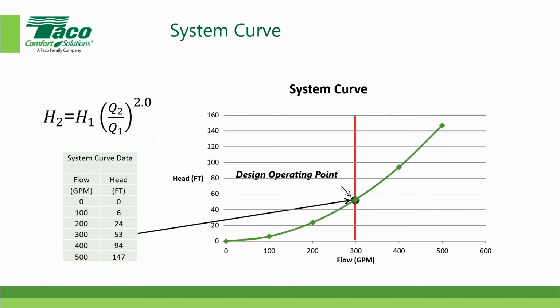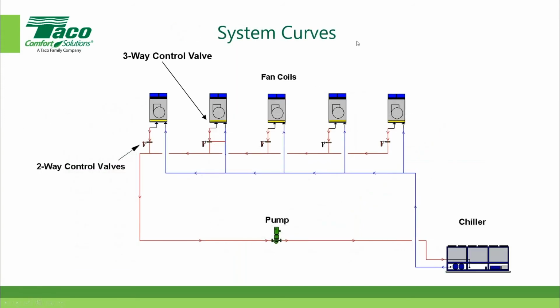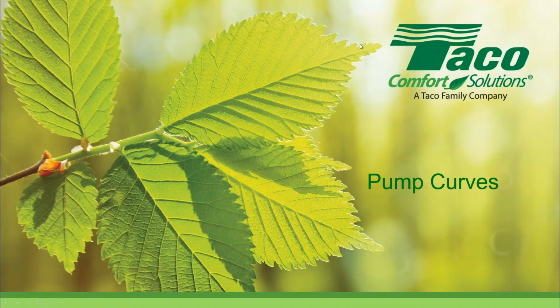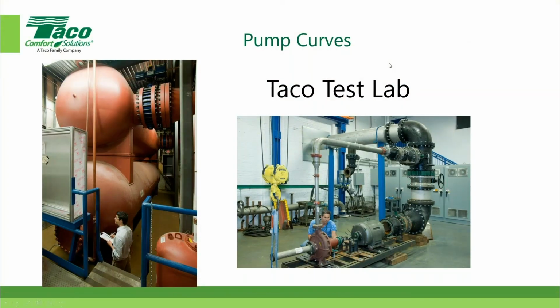Okay. So now let's go on and see what it takes to generate a conventional pump curve. So getting back to our pump curve, here's what we do. Now, most people might think that pump curves are created mathematically, but they're actually not. They're created by measuring the pump performance in a mechanical test lab.